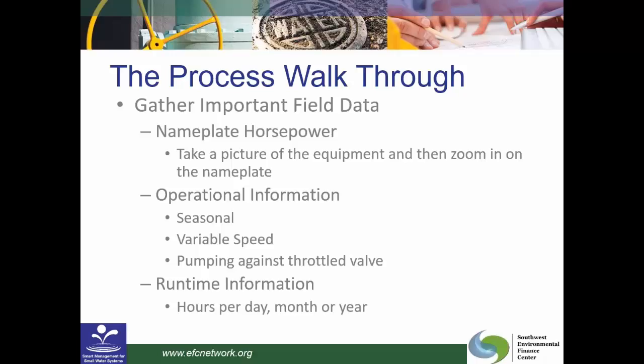And then if you're pumping against a throttled valve, you are essentially taking a pump that's oversized, throttling it down with the valve. So you're using all of this energy to move all of this water, and then you shut it down with a valve. So knowing that you're pumping against a throttled valve will help explain some of the energy consumption.